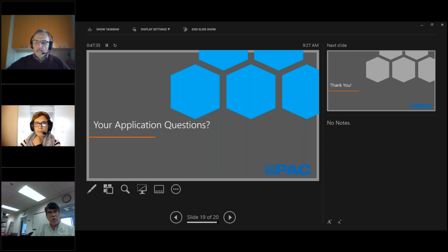Okay, so I'm trying to get this with the webcam. On the sensor itself, you have a block deflector. That's simply removed, and that will give you access to the piston. This block deflector remains in here so that the piston does not shoot out into the process line. It also works to divert flow into the sensor chamber itself.